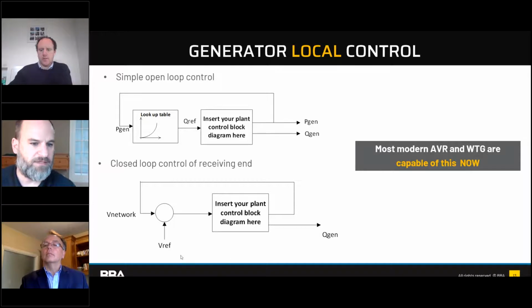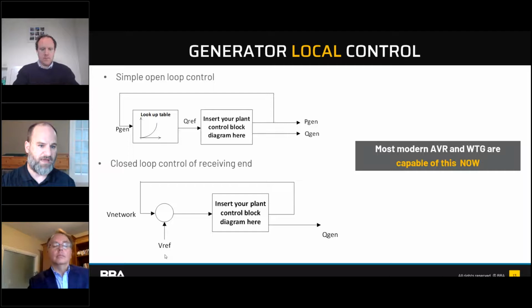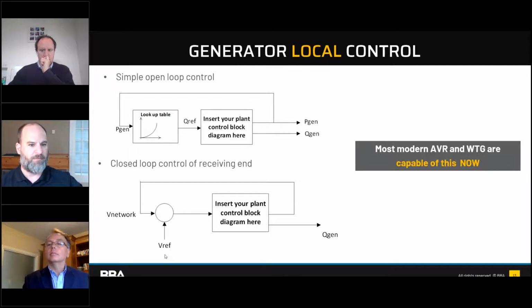If you want something fancier and closed loop, you can take that VREF coming in - that can be sent directly from a control room, saying here's the system I want, or it can be pulse up, pulse down. Most of the time it's sending out the same signal every 30 seconds; it's not changing. But the minute it sees wind variations, the voltage is automatically starting to self-correct. The sending side starts to come up to keep the receiving end where it needs to be, so you've got the post-contingent delta V.